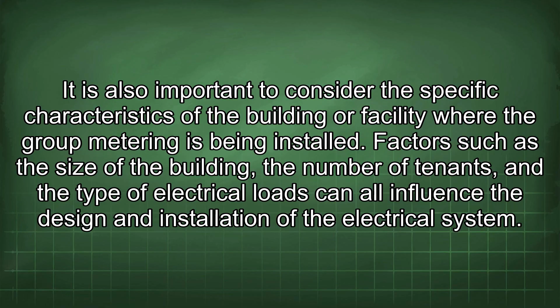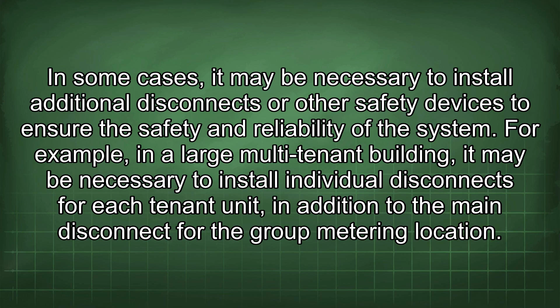In some cases, it may be necessary to install additional disconnects or other safety devices to ensure the safety and reliability of the system. For example, in a large multi-tenant building, it may be necessary to install individual disconnects for each tenant unit in addition to the main disconnect for the group metering location. This would allow for the isolation of individual tenant units without affecting the power supply to the other units.